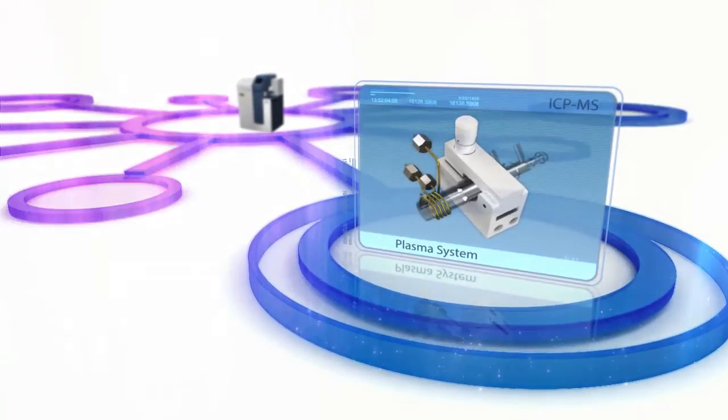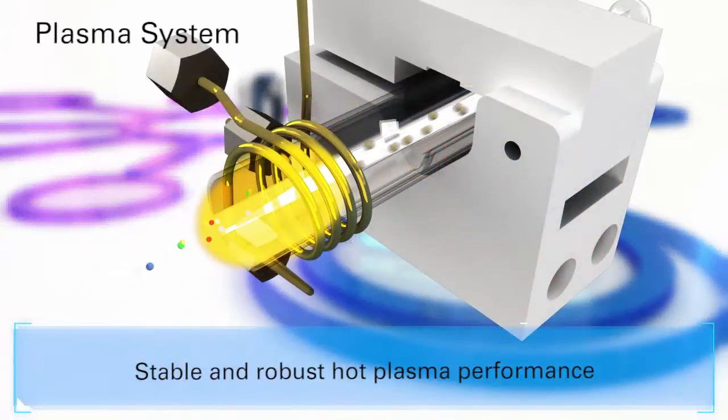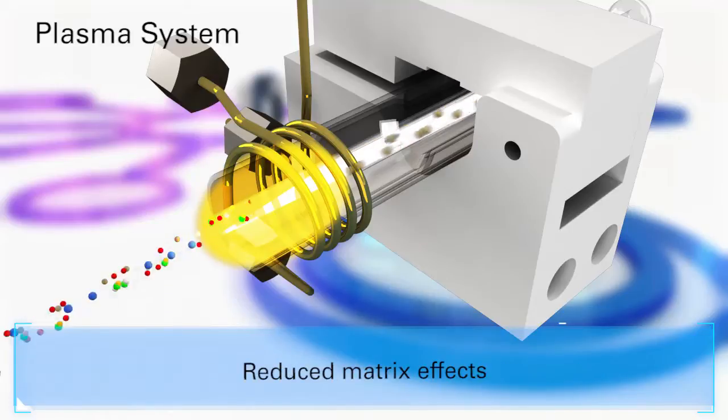Plasma System. The Aurora's inductively coupled plasma incorporates a highly efficient solid-state RF system with patented interlaced coil design that delivers exceptional plasma performance.